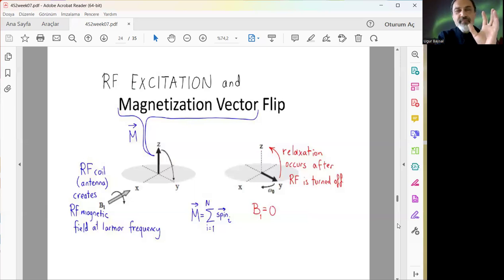Anyway, so now we have a DC magnetic field, the static magnetic field B0, as well as the response to that static magnetic field by the spins of the tissues or body, with a cumulative, invisible magnetic field, M, the magnetization vector. So in all magnetic resonance imaging systems, technical people concentrate on the B0, B1, and M fields. So we don't care about individual tiny little hydrogen protons or whatever, okay?